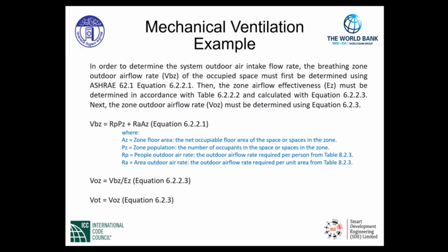6.2.2.2 and calculated with equation 6.2.2.3. Next, the outdoor airflow rate in the zone that's indicated as V sub OZ must be determined using equation 6.2.3. This is the process for calculating the minimum airflow rate that must be designed to be introduced into the air distribution and conveyed to the breathing zone for our example.